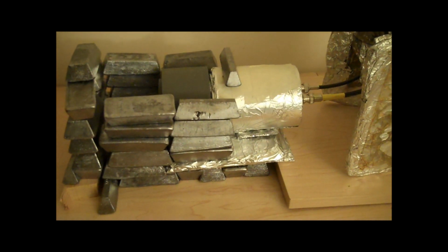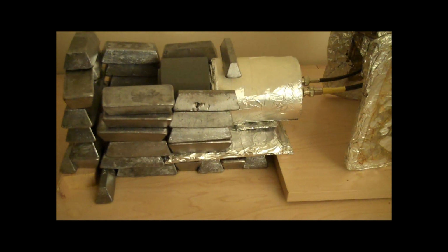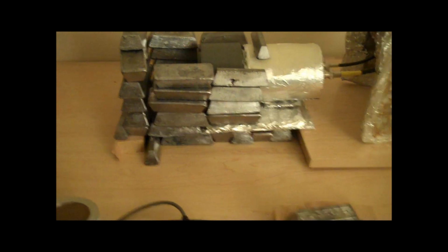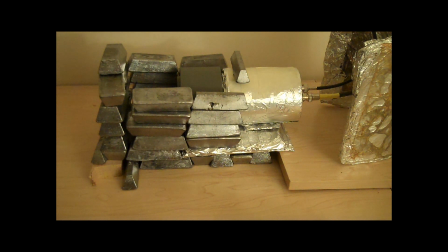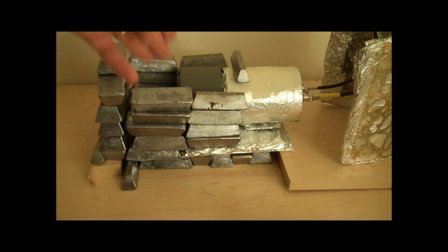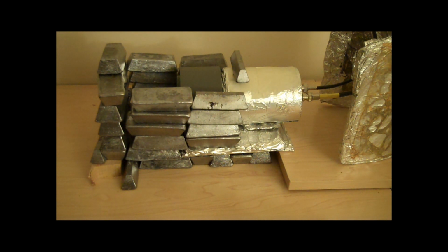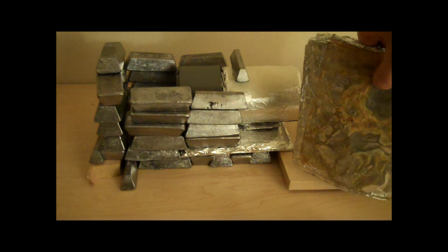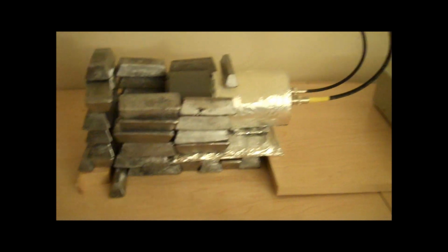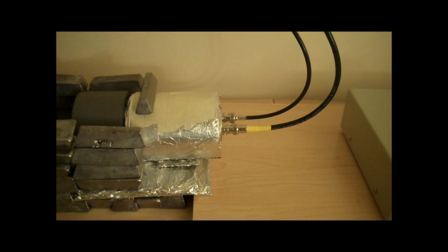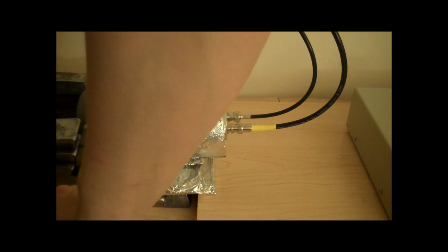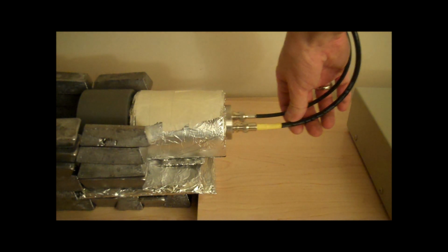But there's more that it can do, and there's a little bit more complexity to how it works. Let us pull the scintillation detector itself out of the lead. Now, if you're curious, the reason that the scintillation detector is contained inside of lead, and encased, if you will, is so that the object that's being placed inside of the chamber, which is right here, will be virtually the only radiation that strikes the detector. Otherwise, the detector is so sensitive that it will detect other things as well. We will remove the lead that is in the back, and we will move the camera over and focus it down towards here, where the actual detector itself resides.